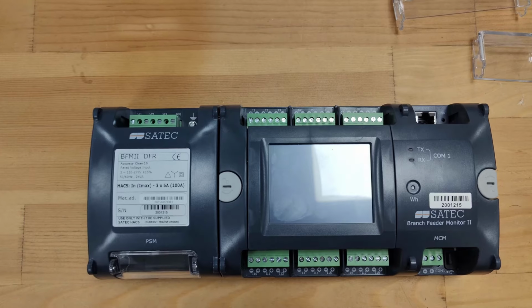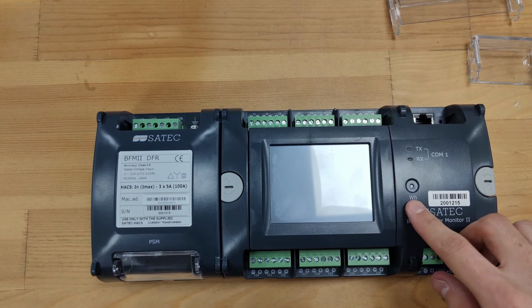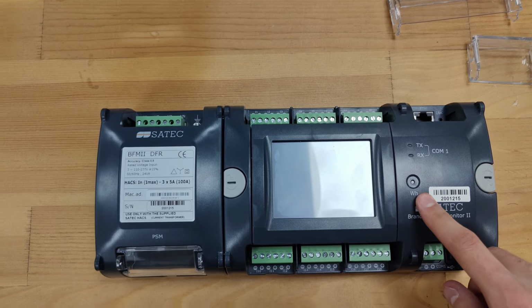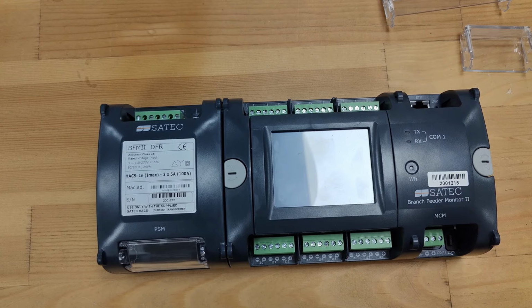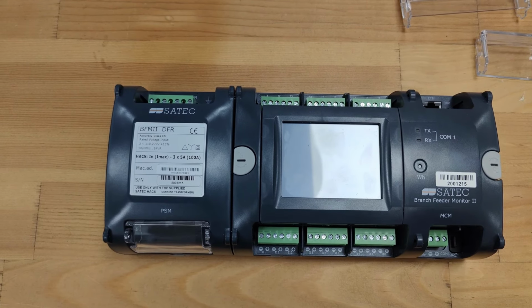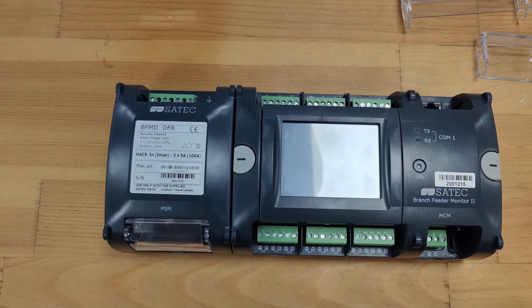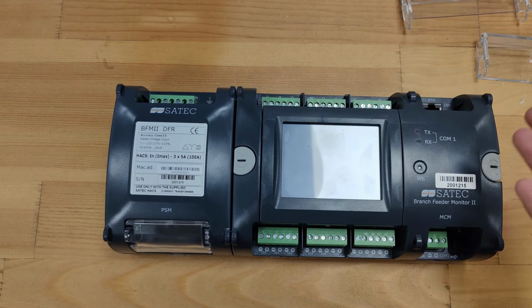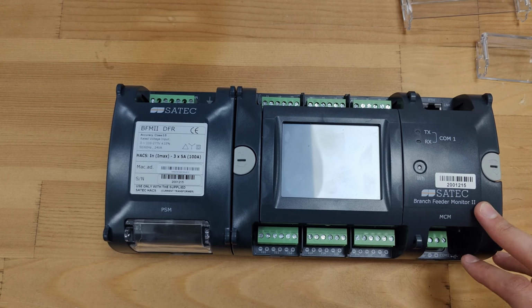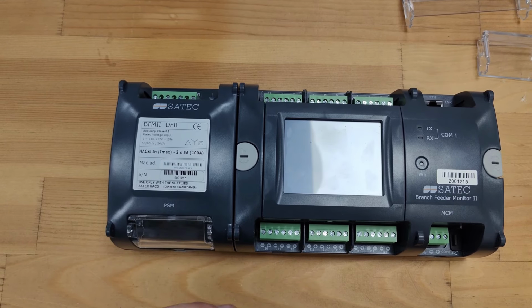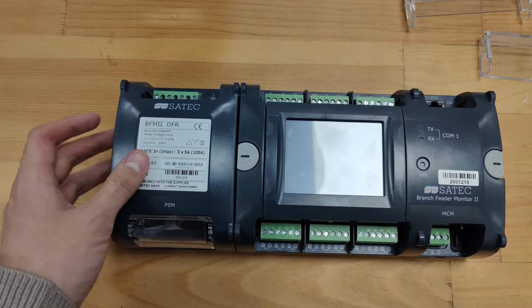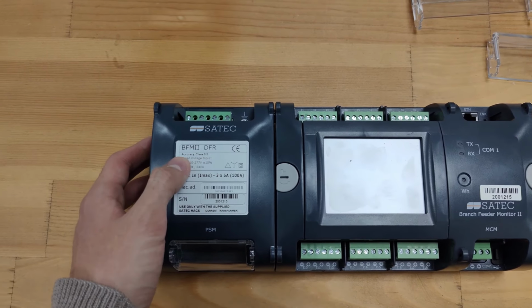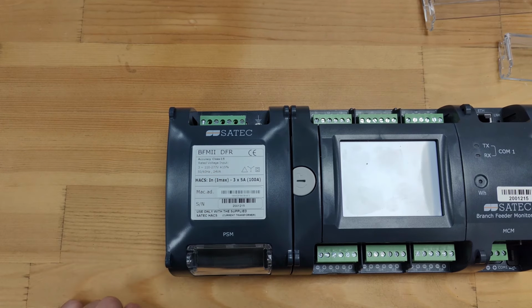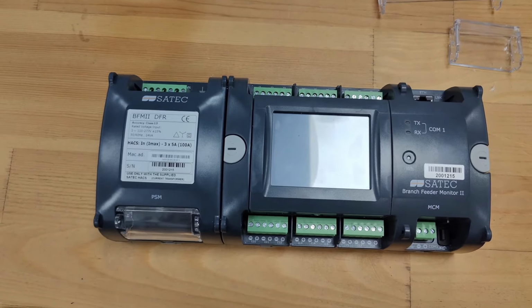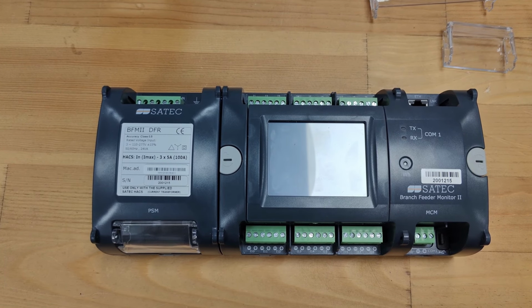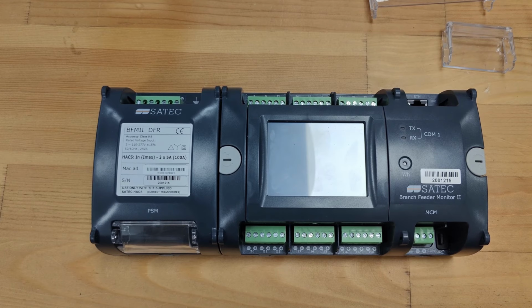Also, we have here this indicator. It's called the Wh indicator. On the panel of the device, it shows the registration of watts consumed or generated. It allows quick verification of the device in case of verification by metrological services. The voltage module displays a label with the necessary information about the device configuration, operating parameters and measuring ranges of current and voltage, as well as the accuracy class of the device. All BFM devices have accuracy class 0.5C.